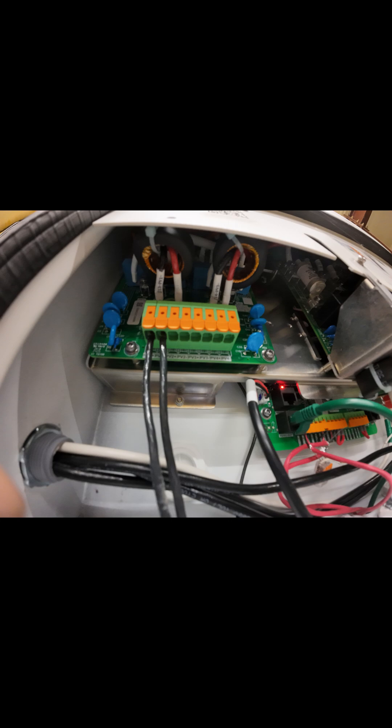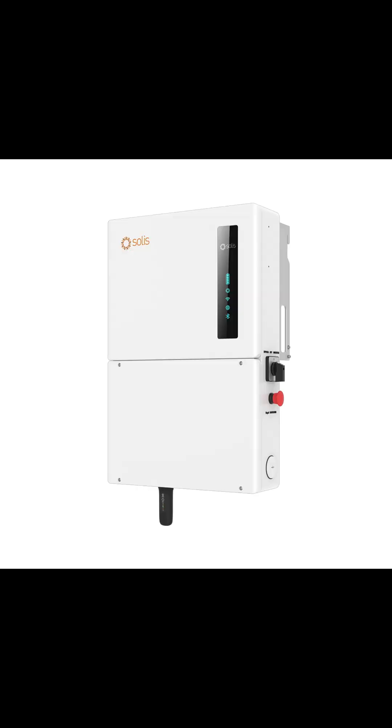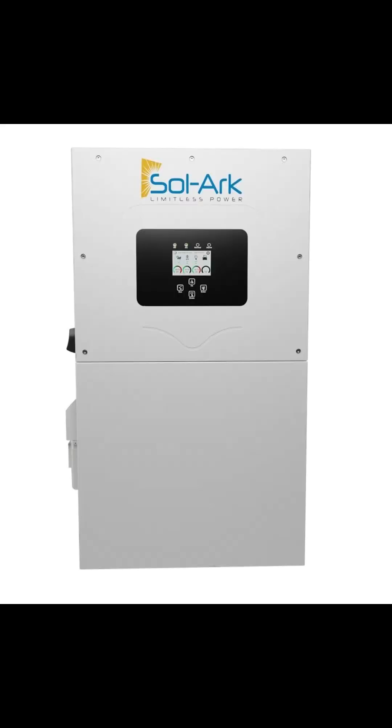Each Solis S6 has four MPPTs at 16 amps per string; two units give you eight MPPTs total. Sol-Ark has three MPPTs, two strings each, with higher amps per tracker. Need lots of small strings and layout flexibility? Solis shines. Running a few beefy strings? Sol-Ark's higher MPPT current is handy.